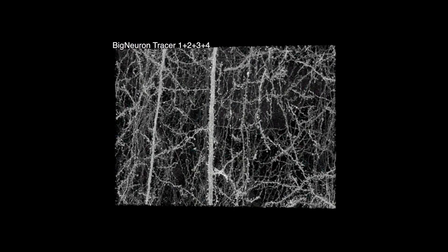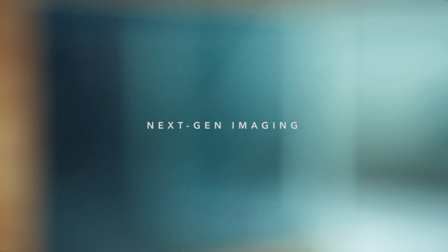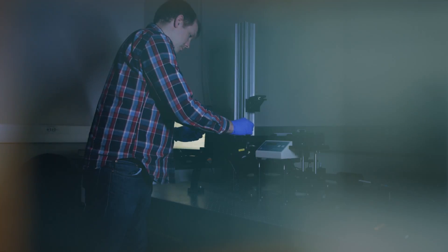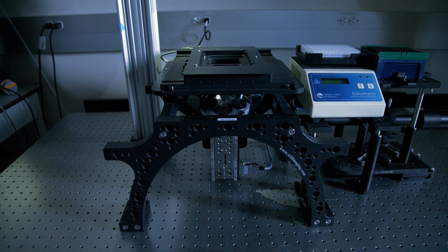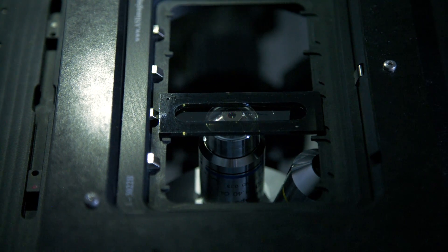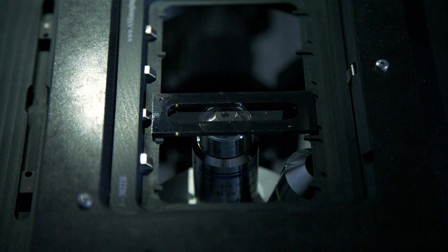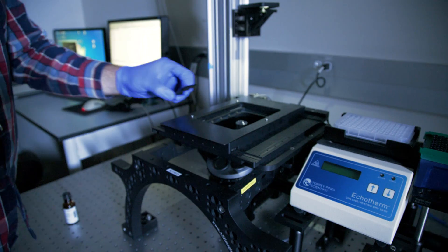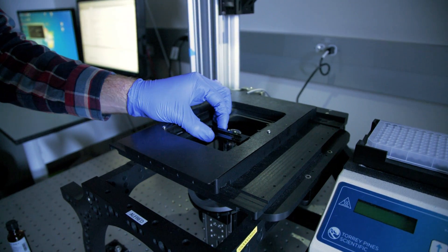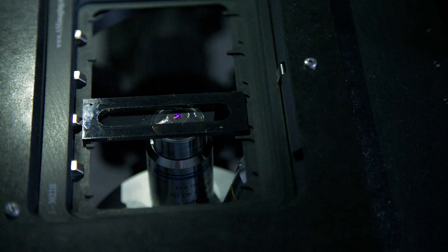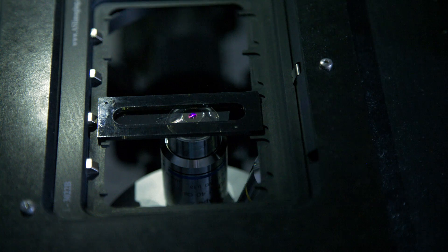That can be stacked back together, and we then have a reconstructed image where we're able to look at the synapses, the cells, the dendrites, the axons, and see what they're made of and how they're related to each other. I work on designing the next-generation array tomography microscope that takes pictures of ultra-thin sections at a much higher rate. State of the art five years ago took about 900 pictures an hour. The microscope we've constructed at the Allen Institute takes about 10,000 images an hour — roughly 100 times faster.